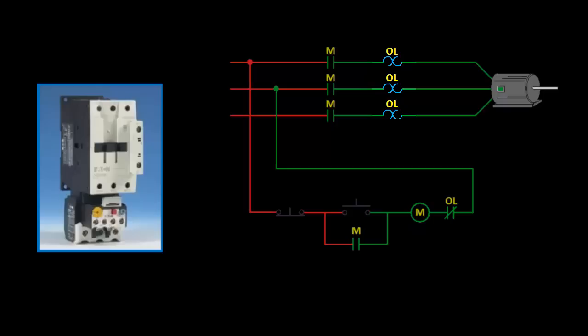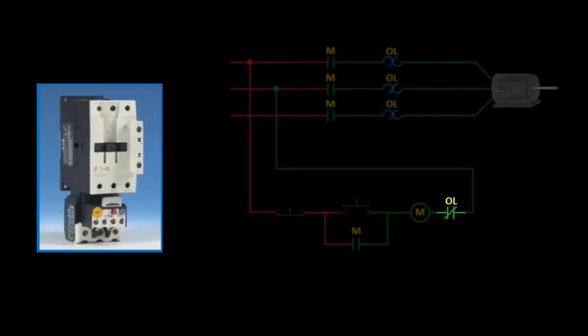It's a common misconception to think that this portion breaks the power circuit, but there is always continuity inside the overload relay. We rely on the normally closed contact in the control circuit to open up, dropping out the contactor.